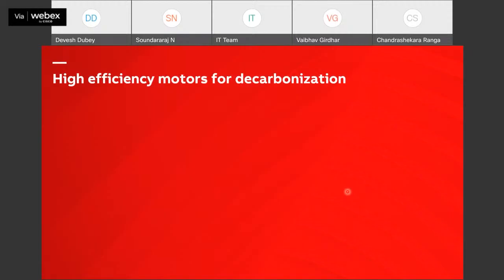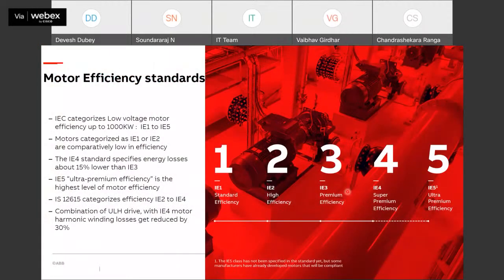Now coming to the point of motors, how the motor is going to support decarbonization with high efficiency motors. The motor efficiency classes set as a standard by IEC are IE1 to IE5 up to 1000 kilowatt. Motors characterized as IE1, IE2 are low in efficiency. When we go to IE3 and IE4, if we jump from IE3 to IE4, it will definitely have specific energy losses less by approximately 15%. IE5, ultra premium efficiency, is also available nowadays.